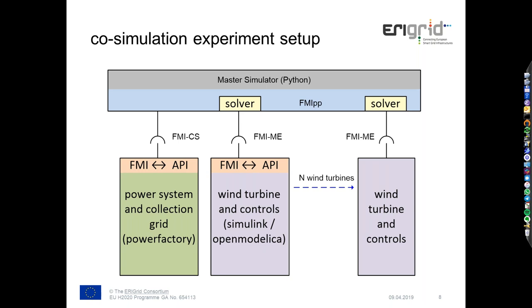Power Factory is run in co-simulation mode, connected to the Power Factory API, doing the time stepping. The wind turbine models and fault ride through models are then connected to the FMI++ library with a separate solver. So each wind turbine has two FMUs: one for the vector controller and one for the fault ride through finite state machine controller.